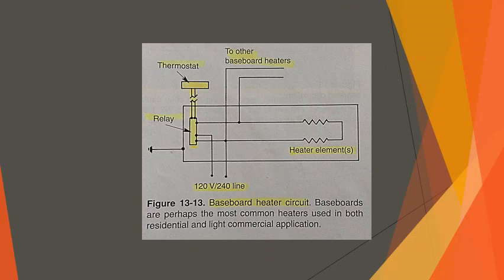Heater circuits. A heater circuit is a schematic drawing showing how the heater operates and the proper way of connecting it to the electrical system. Because of the variations in types, makes, and models of heaters, it would be impossible to describe all heater circuits possible. However, the common types of heaters available for home or office installation are fairly similar. Figure 13-13 shows the circuitry commonly found in baseboard units. Generally, these may be wired for 120, 208, or 240 volts. Circuits must be properly grounded.